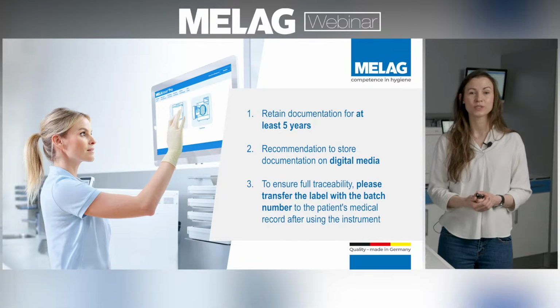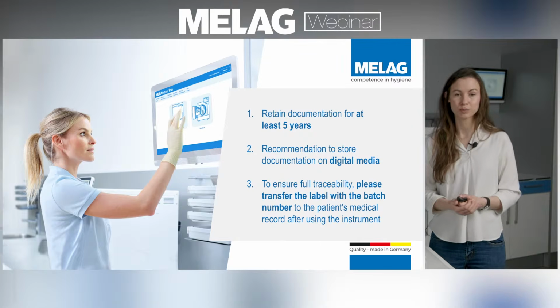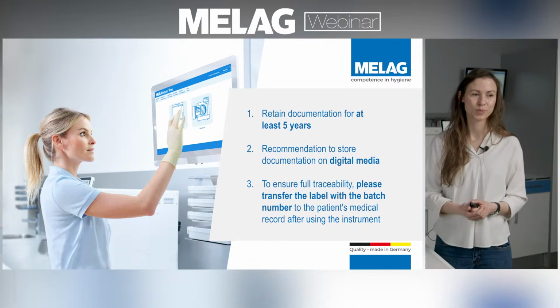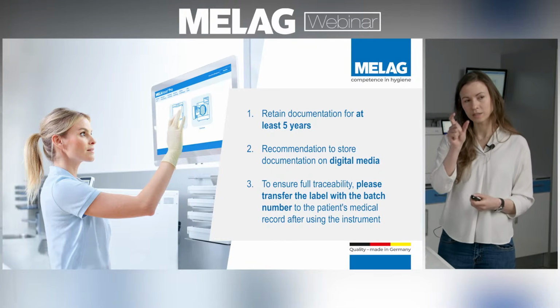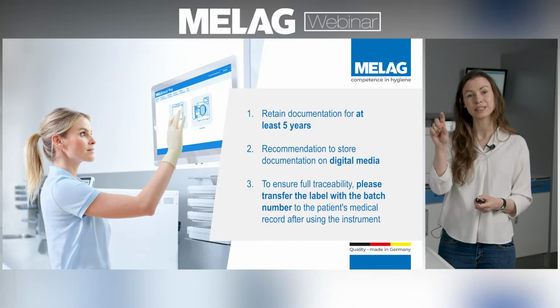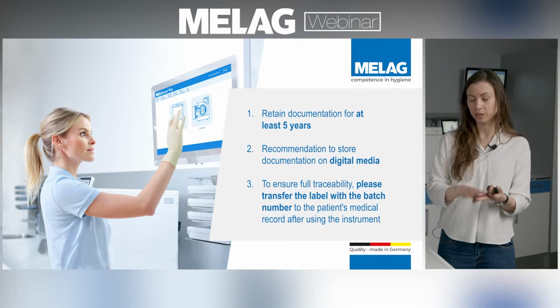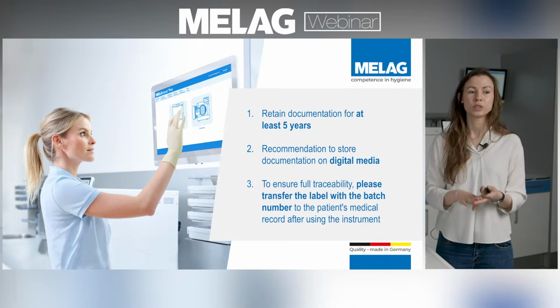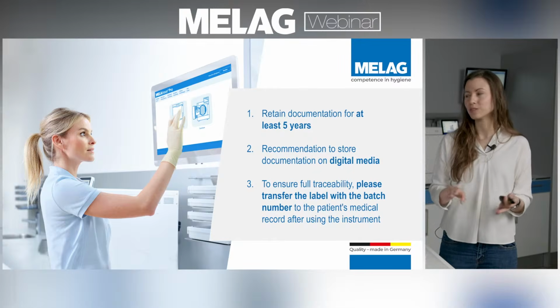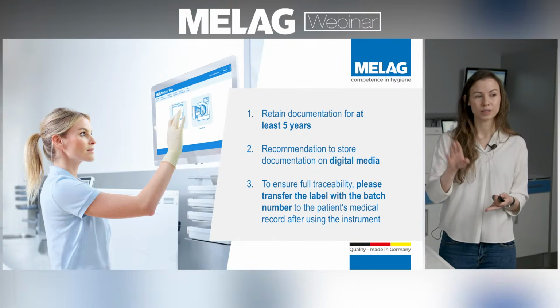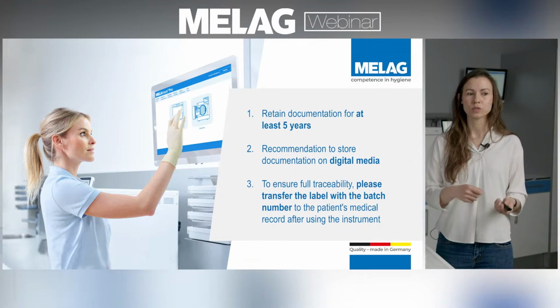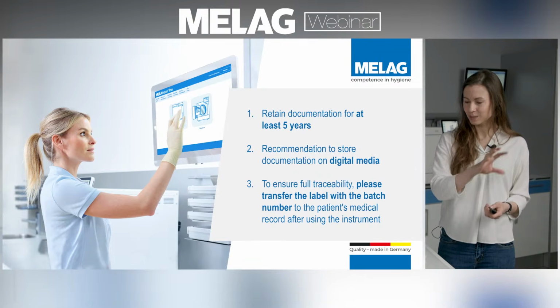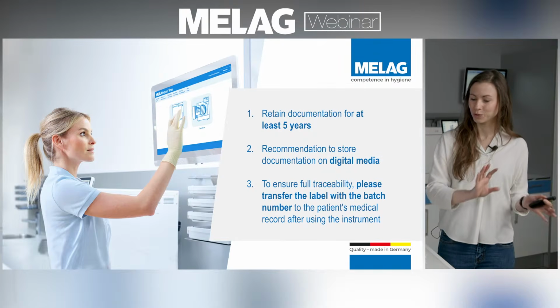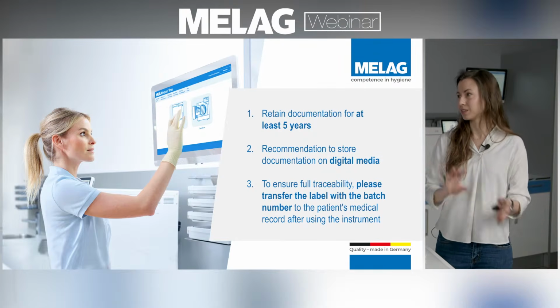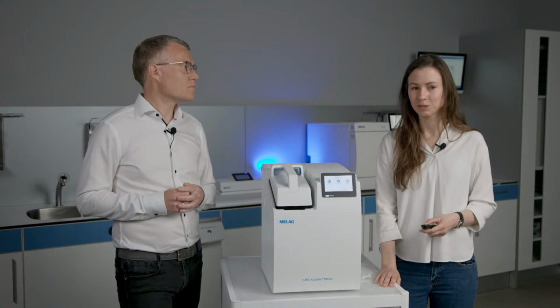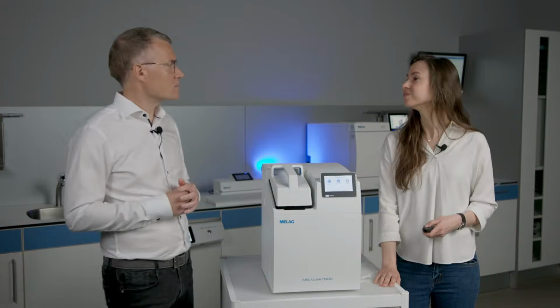And then once you've documented the correct reprocessing and sterilization of the instruments, you have, for us, a little label that is put onto the packaging of the sterilized instruments. You can use this, and it's advised to transfer it into the patient's file once it is used, just to make sure that the entire process and the single instruments which were used with the patient are documented in his file as well. So it's 100% traceable. Like a tracking system. Exactly.